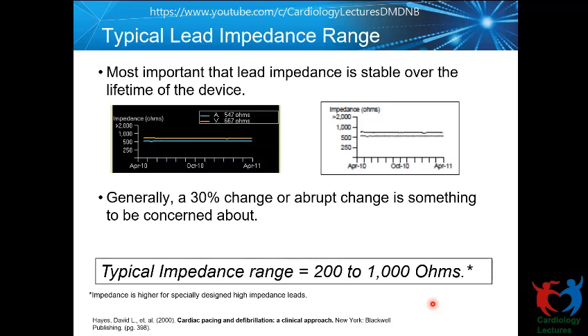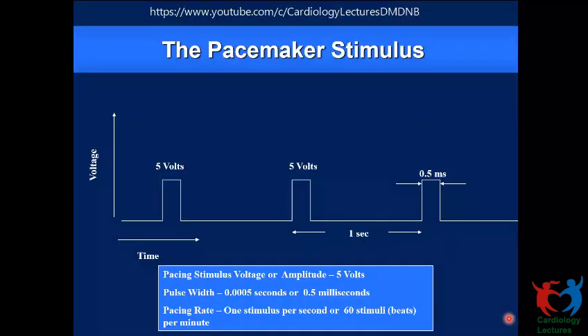But as I said, the current pacemakers monitor the impedance and give a graph on the home screen of the programmer. You can observe that as long as it is stable, we can assume that the lead is in good condition, and when thresholds are good, that is good. But as I said, when there is a sudden change of impedance of more than 30%, it's worthwhile investigating that lead a little more carefully. So that's about impedance and Ohm's law.